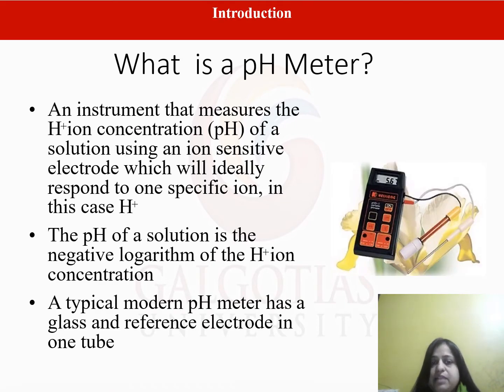It is an instrument that measures the H ion concentration, or we can say pH, of a solution using an ion sensitive electrode which will ideally respond to one specific ion. In this case, that is the H positive ion. The pH of a solution is the negative logarithm of the H plus ion concentration. The typical modern pH meter has a glass and reference electrode in one tube.